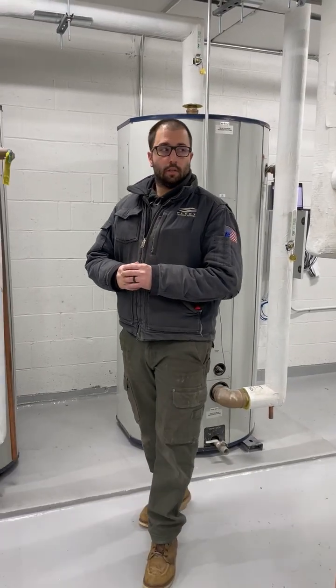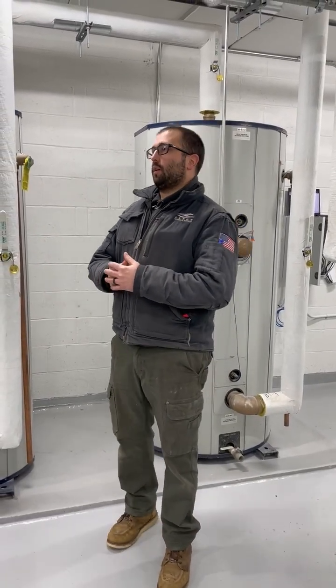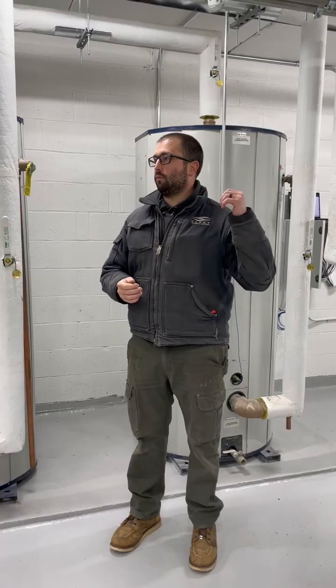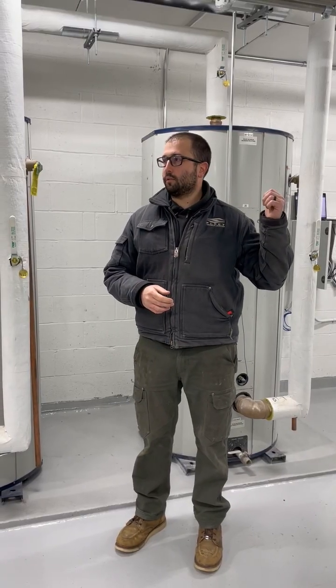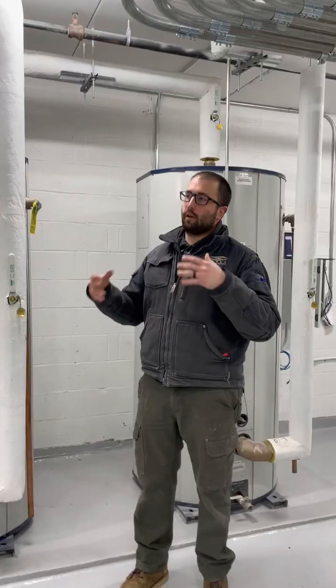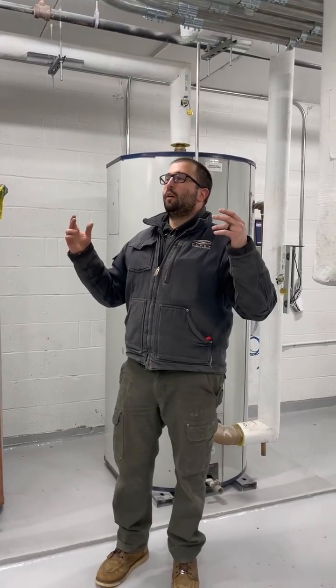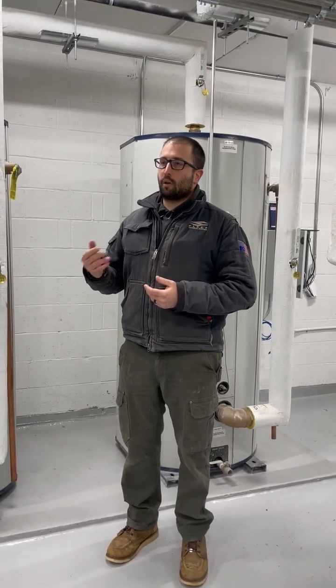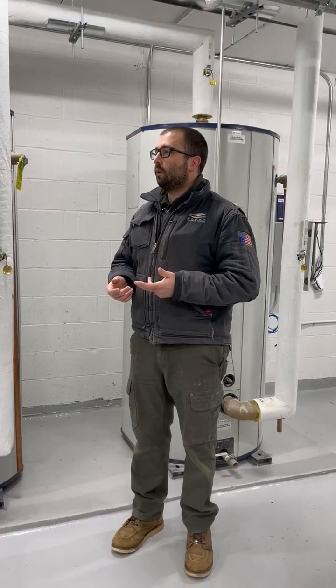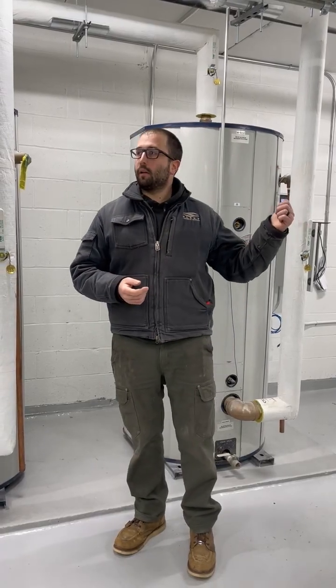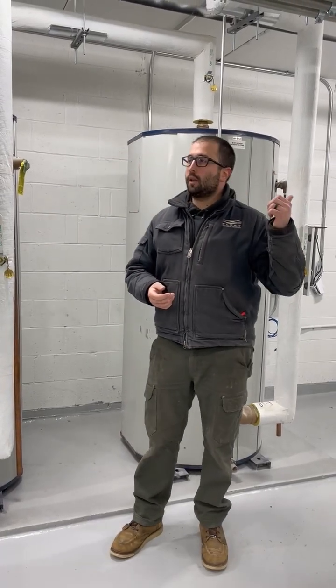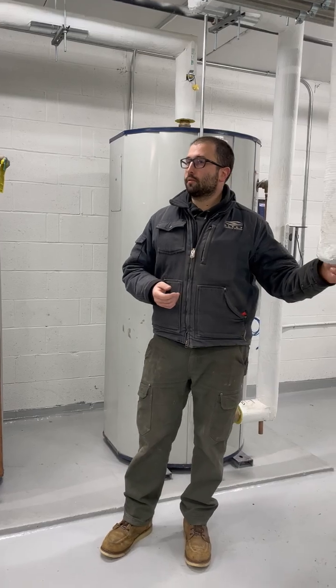So, today we are going to be talking about CO2 heat pumps. On this site you have 3 air source CO2 heat pumps, which means we're taking the cold air from outside, or ambient air temperature at that time. We're putting it through a refrigerant, we're compressing it, and we're creating heat. So from those units outside, each one is 180 degrees coming into these heat exchangers.